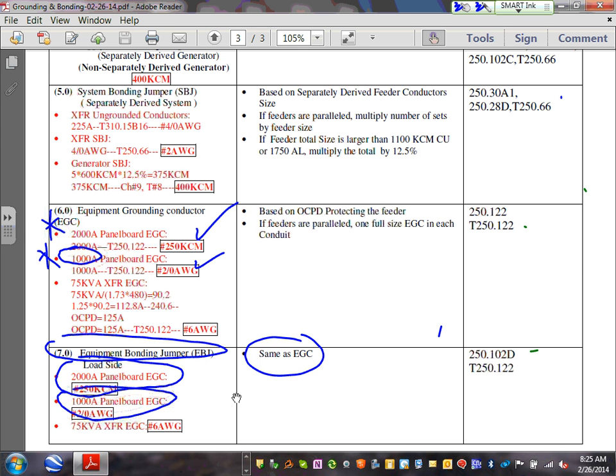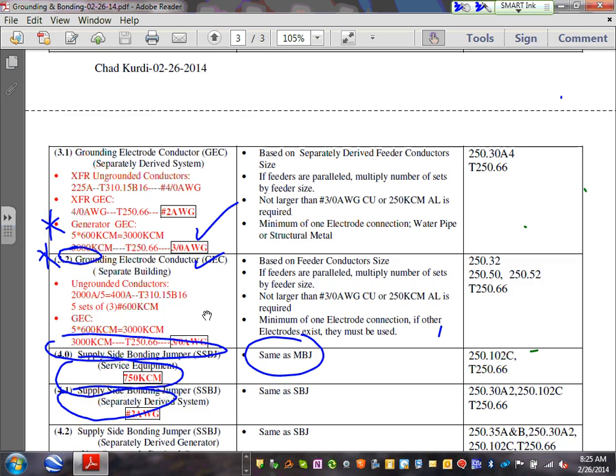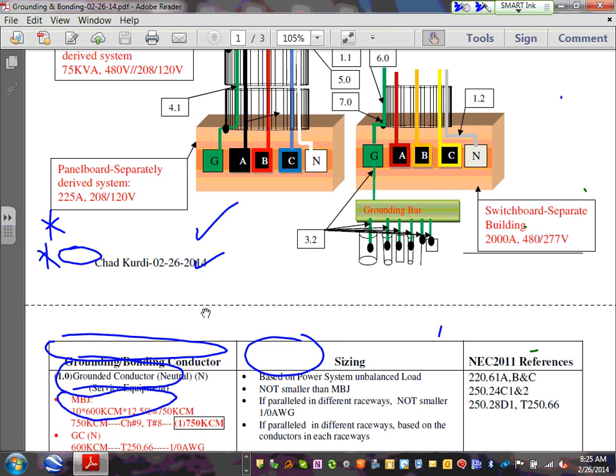Any questions about grounding and bonding at a separate building? Really not a whole lot to it when you follow the rules and regulations for it. So summarize. Here's my third thing that I'm going to do. I size the grounding conductor. I size the equipment grounding conductor. I size the main bonding jumper, and I size the grounding electrode conductor.